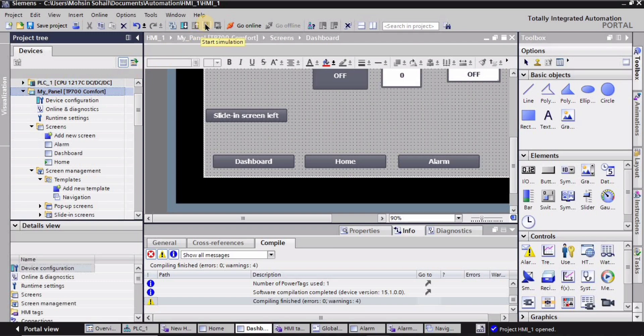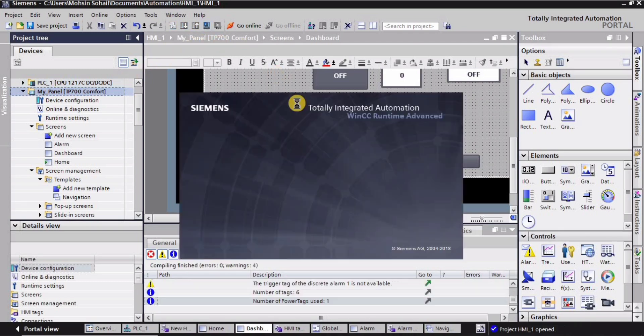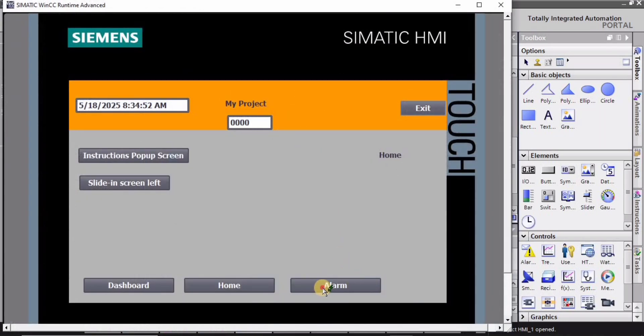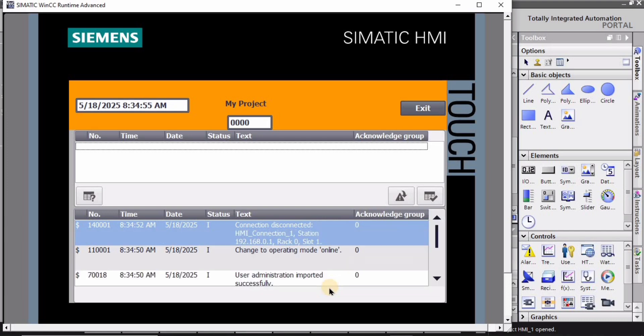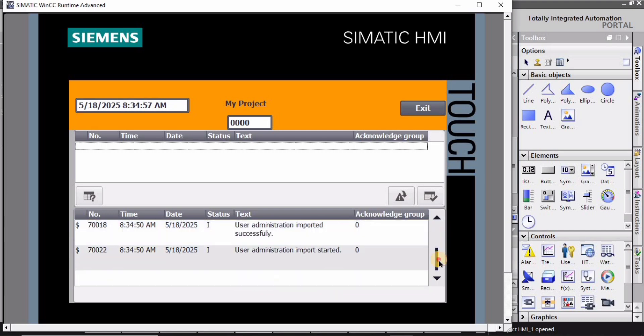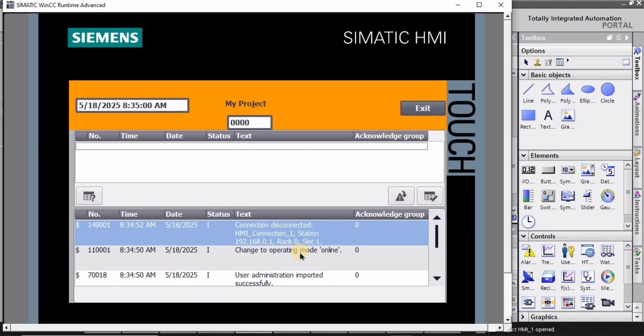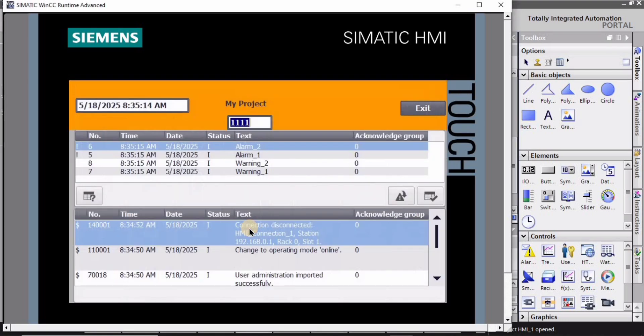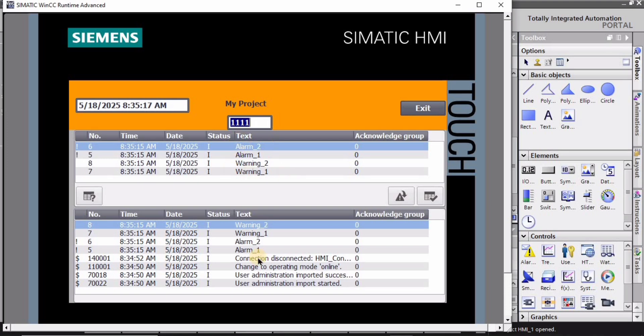I'm going to select the HMI panel and start the simulation. Here we have the button for the alarm screen, so I will select it. On the bottom screen here we have the buffer — these are the history messages. Here we have the computer history messages, and while selecting the format from decimal to binary we have that pattern, so I'm going to select '1111' and hit enter. As soon as I do that I will see the alarms and warnings that we have created, and also in the buffer area as well.